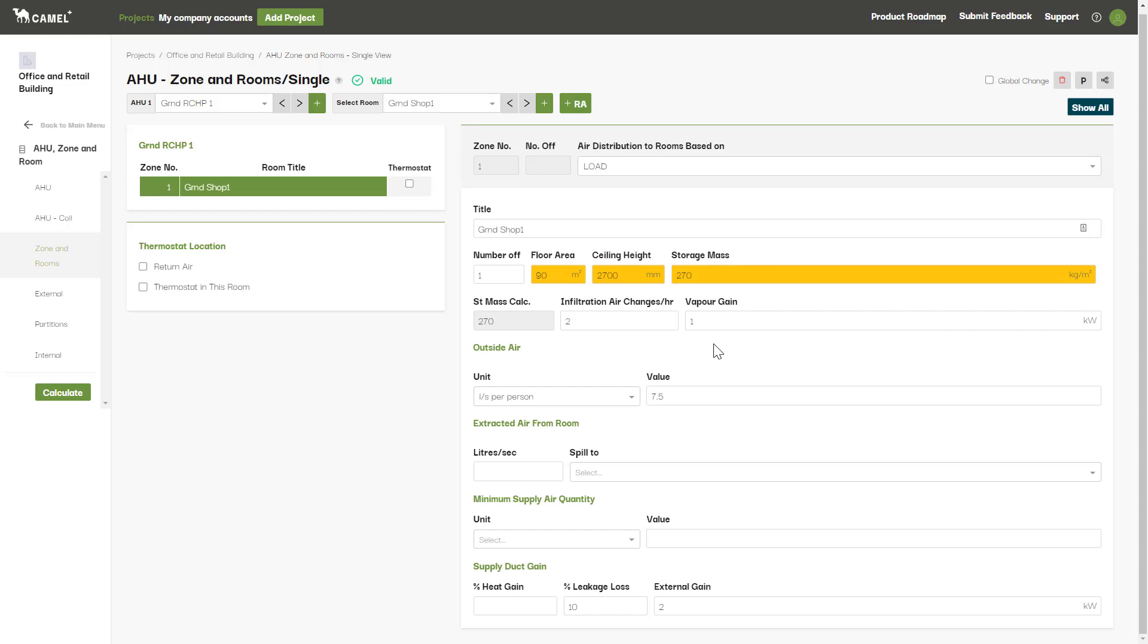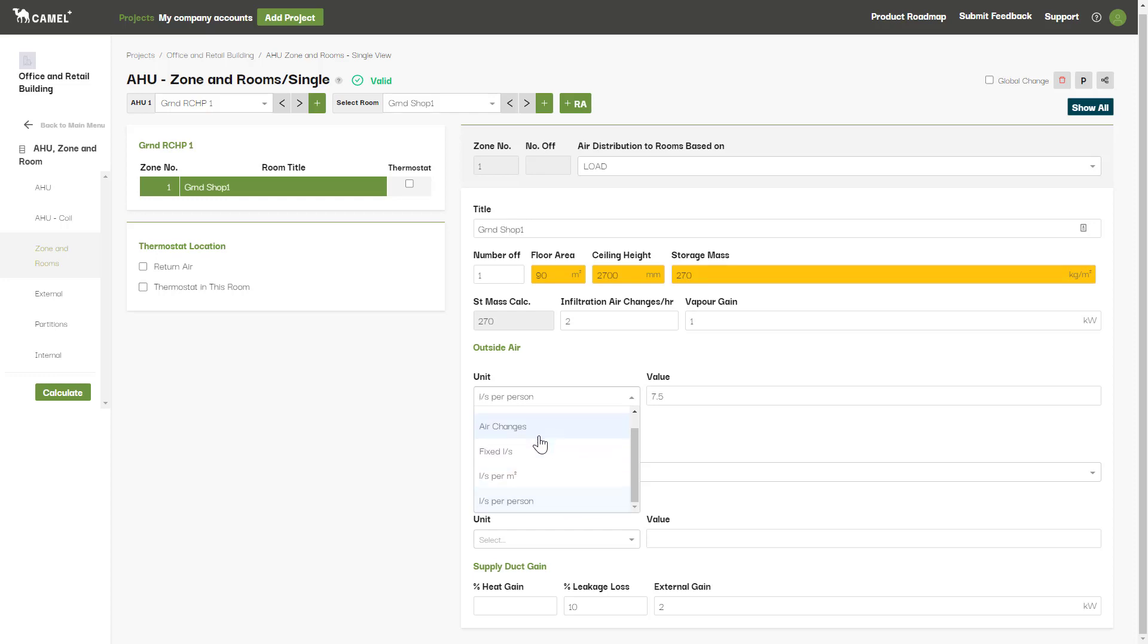If on the AHU screen you selected the enter in rooms option for the outside air, you'll be able to enter in your outdoor air here. There are different units you can choose from for this depending on your requirements. Just note that this is air changes per hour and is based on the floor area and ceiling height entered above, and that this litres per second per person is based on the room occupancy input on the internal screen.